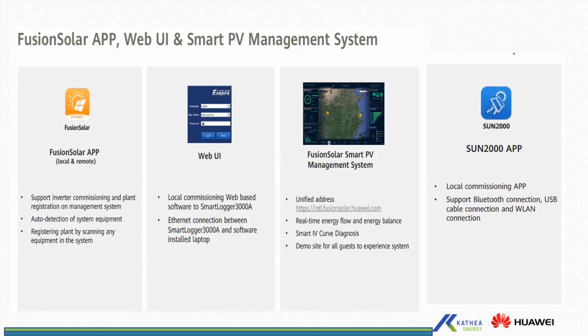and you can use this app for remote monitoring and control. But the control function is limited. Safety settings like the grid code, changing frequencies and all that, those are only limited to local control. And then the web UI, this is the SmartLogger 3000 commissioning page. It's web-based software. So to access this page, you need to be on site and have a connection between your laptop and the logger through Ethernet. And we'll look into it more in our commissioning session tomorrow.